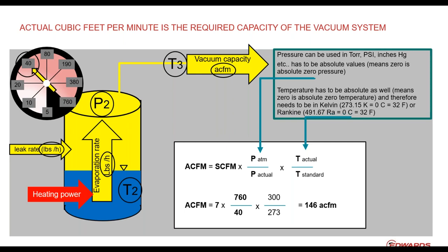ACFM equals 7 SCFM times (760 ÷ 40). Remember, 40 Torr is the vapor pressure of IPA at the temperature I picked — that's the best pressure you can accomplish, so both the evaporation rate and leak rate take the volume at that pressure. You can use absolute values in any unit — psi, inches of mercury — as long as you stay in absolute values, the ratios stay the same. For temperature, you must also use absolute values: Kelvin or Rankine. 273 K equals 32°F. Watch out for that — it's important.